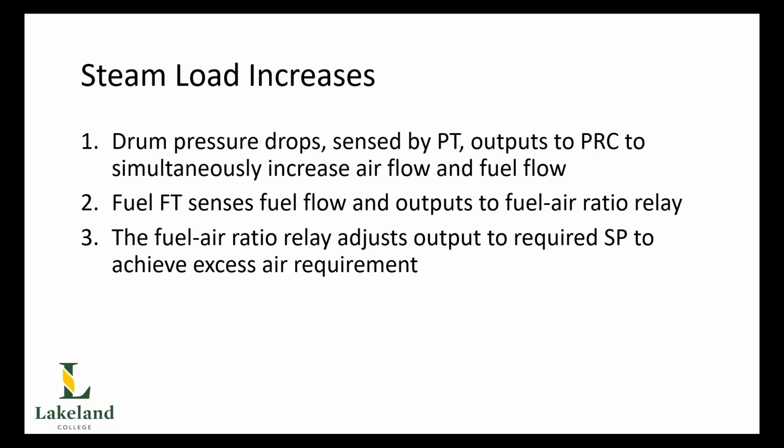The fuel flow transmitter now is going to see an increase in fuel flow, and the airflow transmitter will also see an increase in airflow. Now it's going to output these values through the fuel to air ratio relay, and it will determine what new set point is required in order to achieve our new firing rate and the excess air required at the new firing rate.